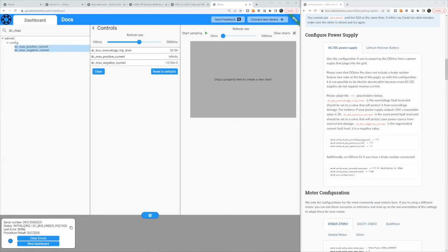Okay, so DC bus overvoltage trip level. It says to put a value above the nominal value of your power supply — this is a safety limit. So I have a 20 volt supply, I'm going to put 30 volts here. I think that will be sufficient to protect the power source from any overvoltage.